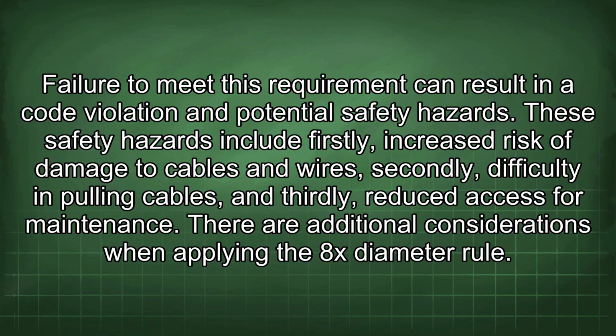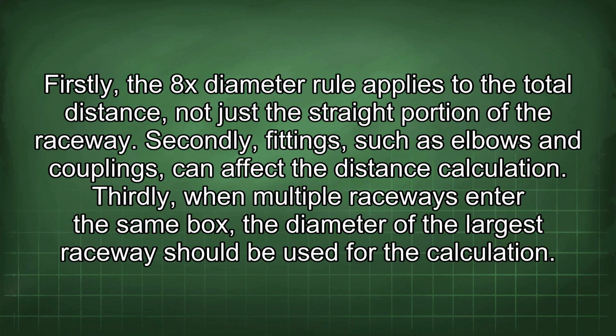These safety hazards include, firstly, increased risk of damage to cables and wires, secondly, difficulty in pulling cables, and thirdly, reduced access for maintenance. There are additional considerations when applying the 8x diameter rule. Firstly, the 8x diameter rule applies to the total distance, not just the straight portion of the raceway. Secondly, fittings, such as elbows and couplings, can affect the distance calculation. Thirdly, when multiple raceways enter the same box, the diameter of the largest raceway should be used for the calculation.